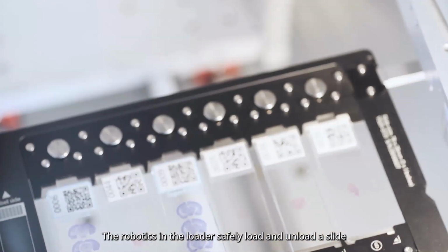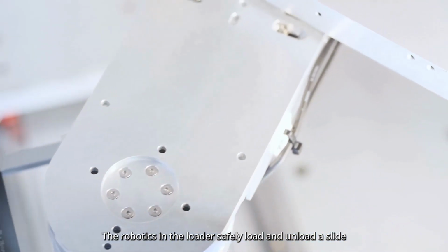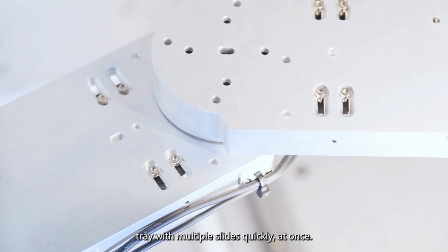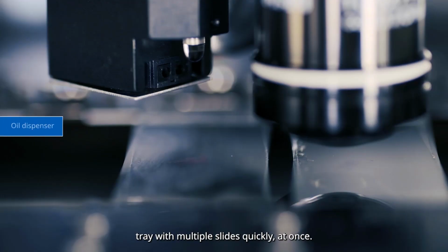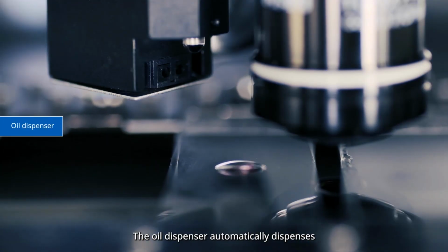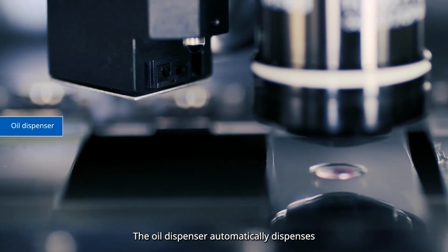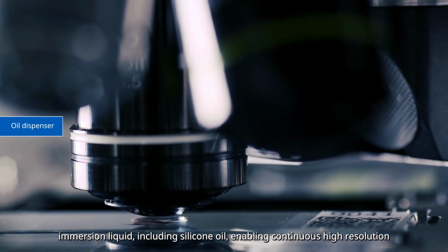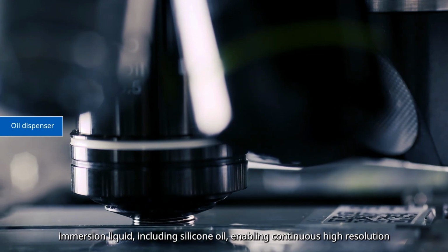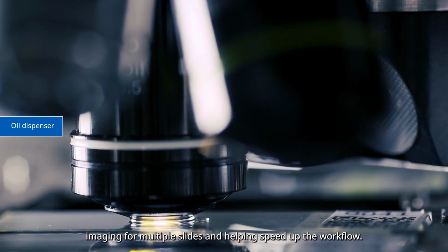The robotics in the loader safely load and unload a slide tray with multiple slides quickly at once. The oil dispenser automatically dispenses immersion liquid, including silicone oil, enabling continuous high-resolution imaging for multiple slides and helping speed up the workflow.